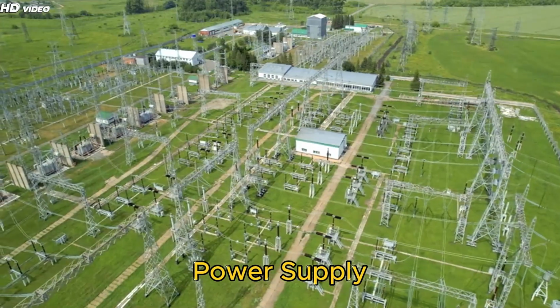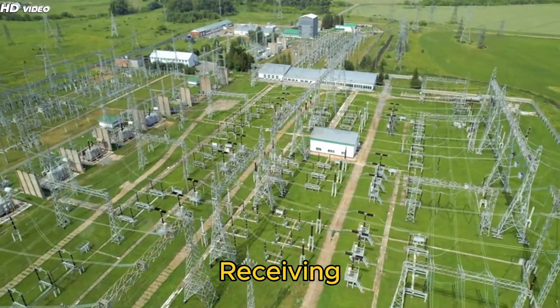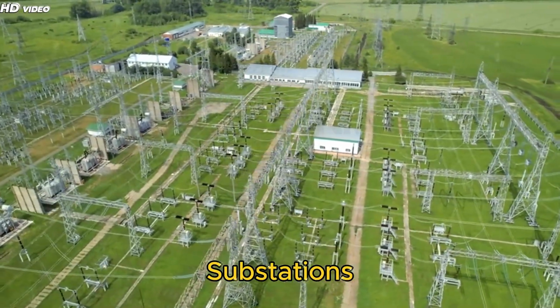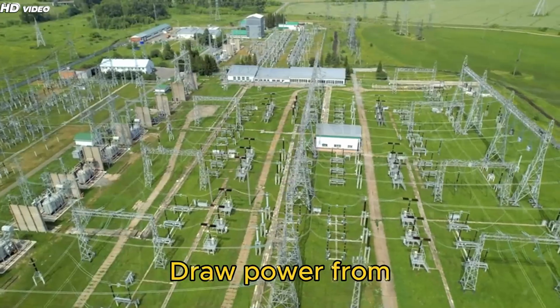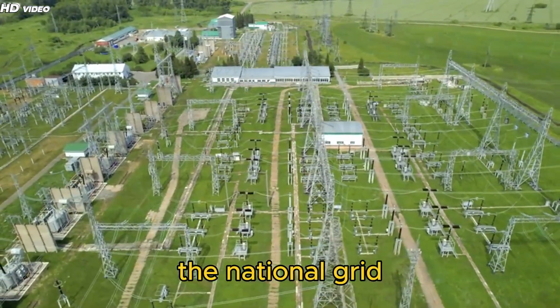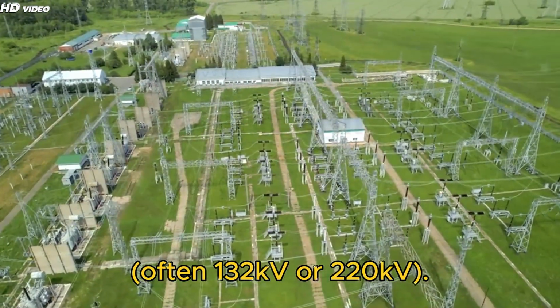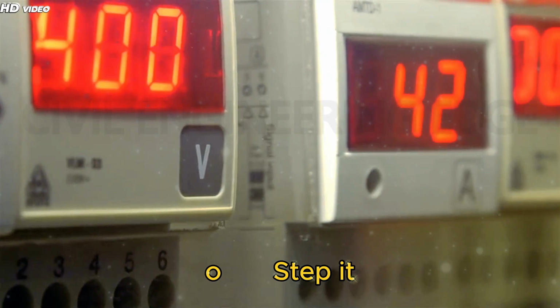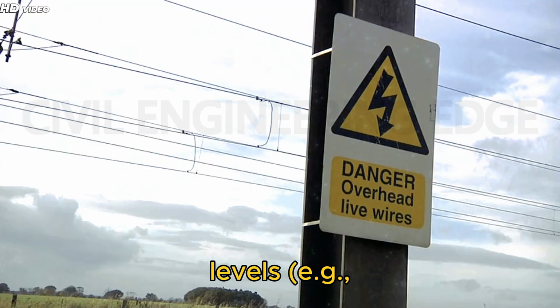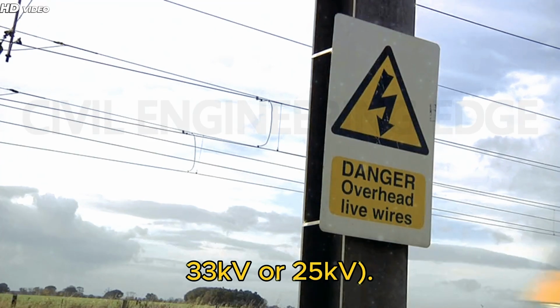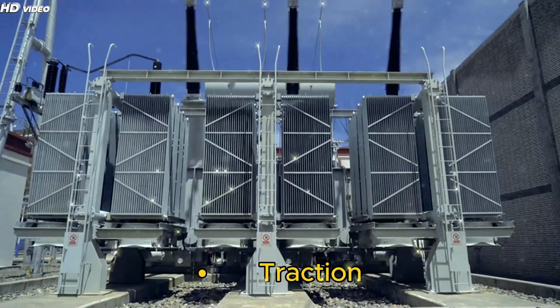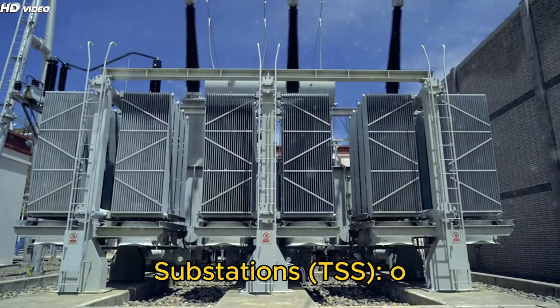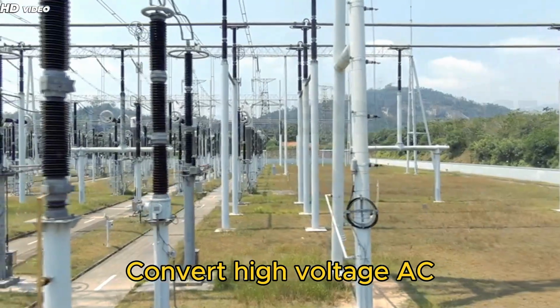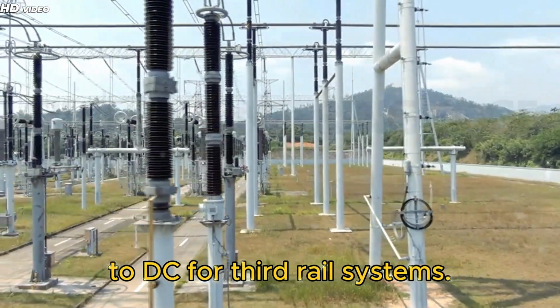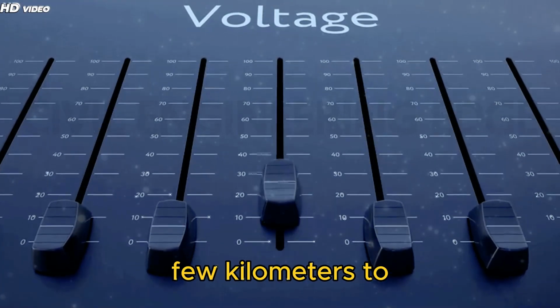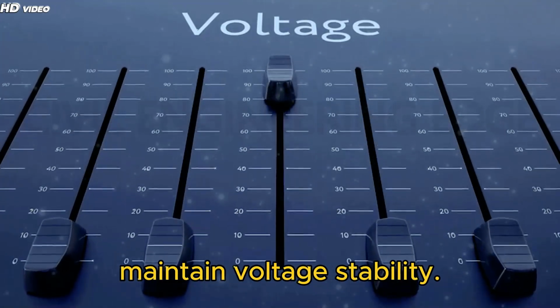Power supply architecture. Receiving substations, RSS. Draw power from the national grid, often 132 kilovolts or 220 kilovolts. Step it down to usable levels, for example, 33 kilovolts or 25 kilovolts. Traction substations, TSS. Convert high voltage AC to DC for third rail systems. Located every few kilometers to maintain voltage stability.